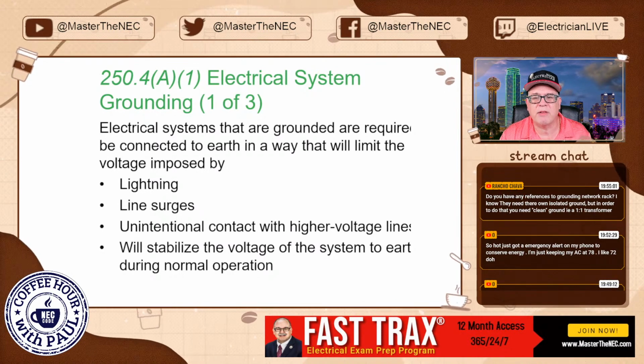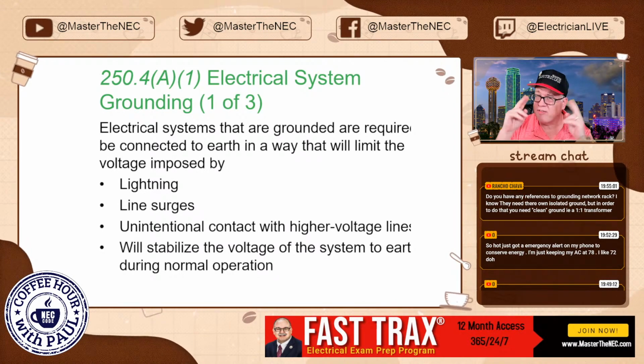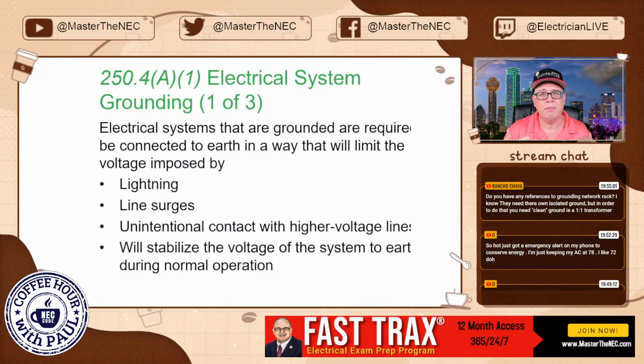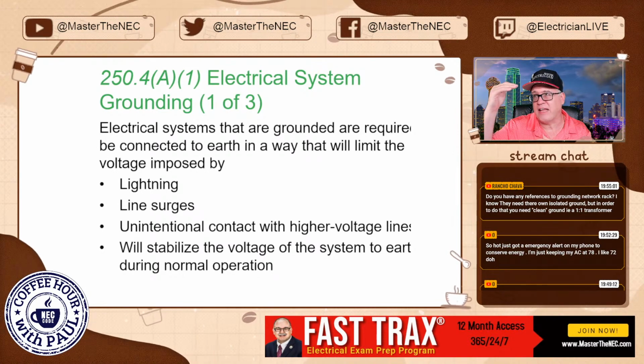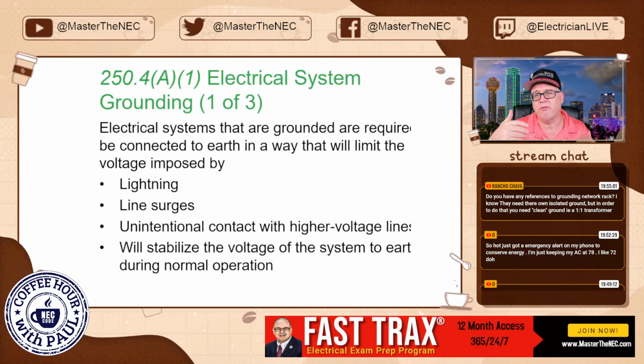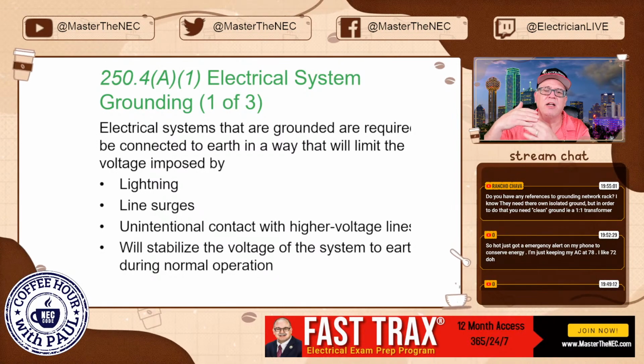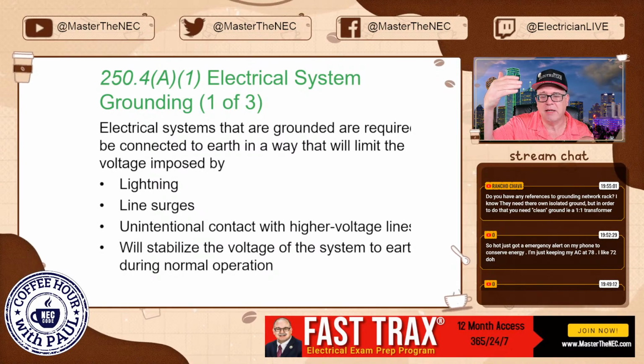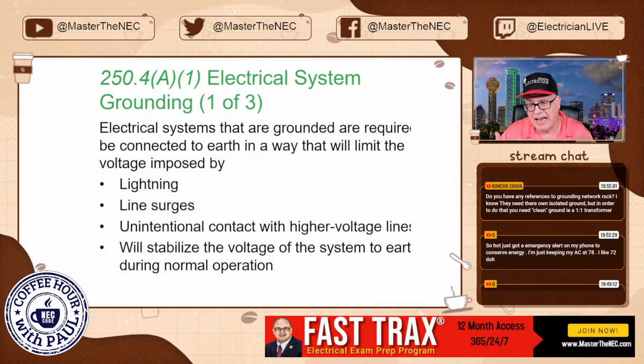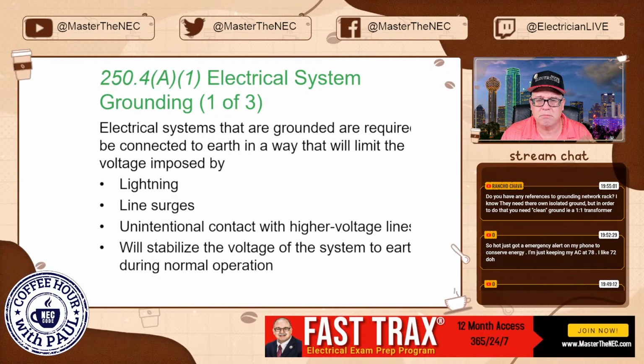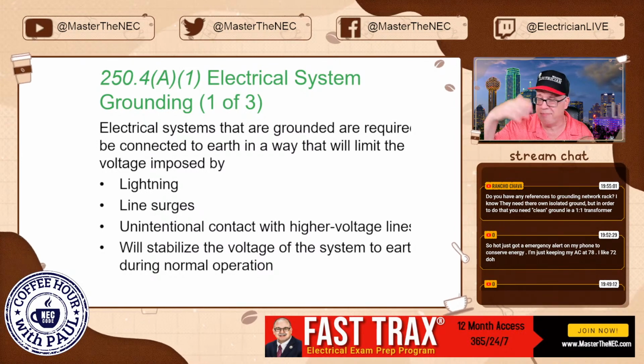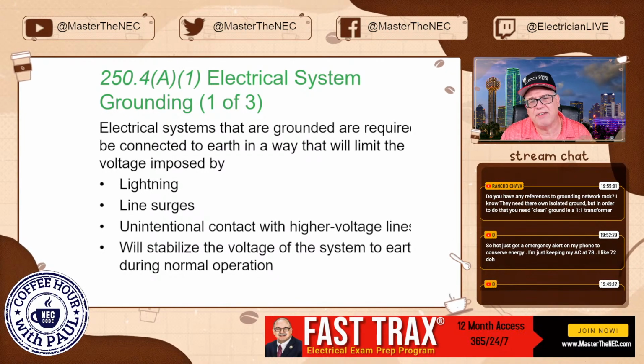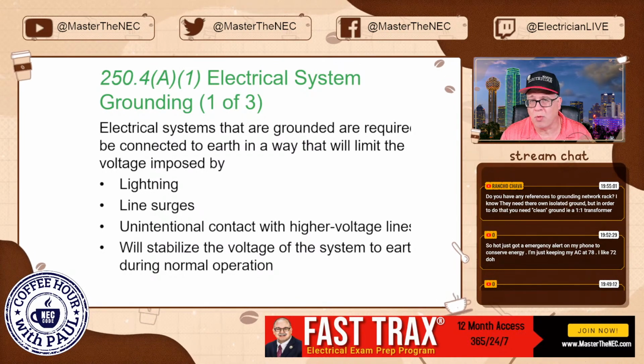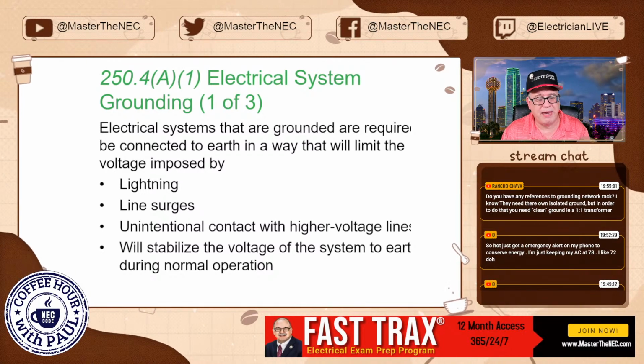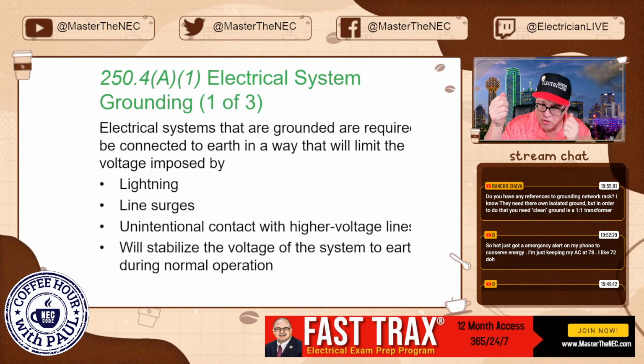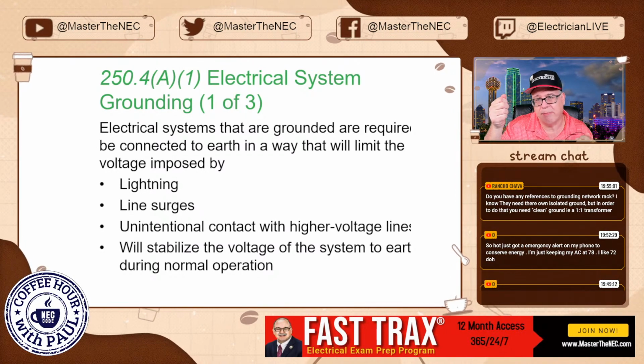You have unintentional contact with high voltage lines. Your low power lines, we say low, but your service drops during a storm could have an issue where the high powered lines, say 7,200, where it might drop down to 120, 240, might cause those lines to come in contact. That's unintentional contact with a higher voltage line. It could come during a storm, a natural disaster, or somebody cutting trees. And then, of course, stabilizing the voltage of the system to earth during normal operations so that our meters work properly. When we make one connection from one of the phases to ground, we get an accurate reading, those types of things.